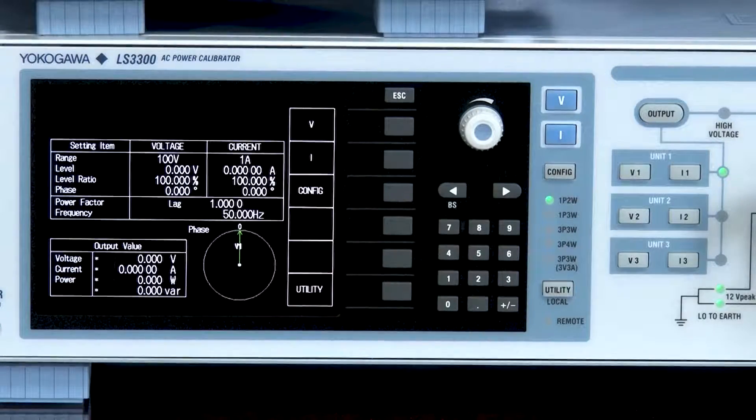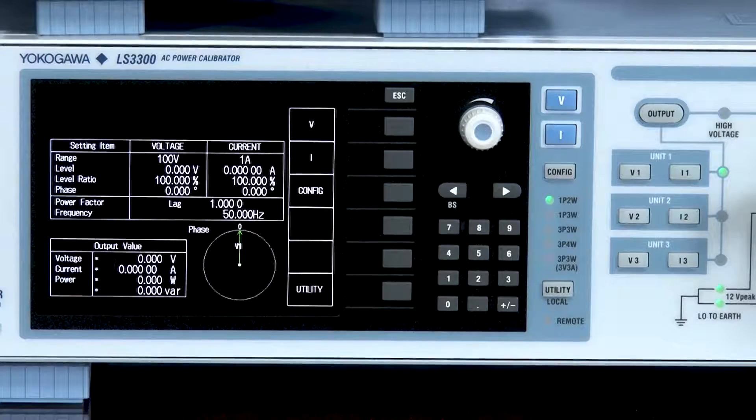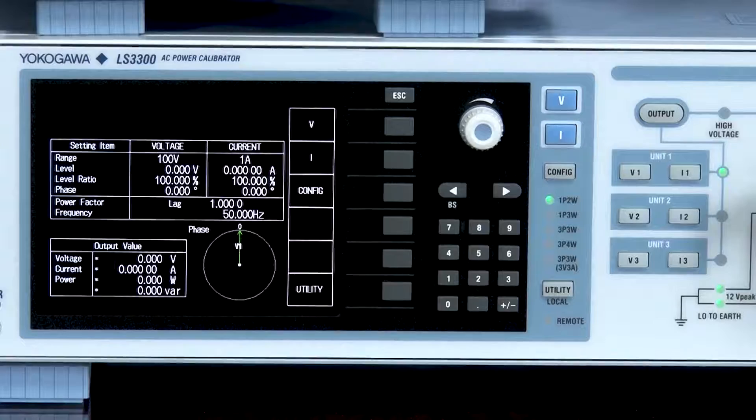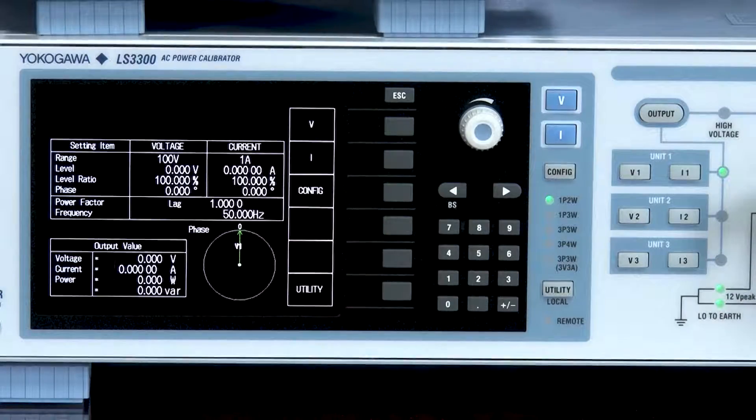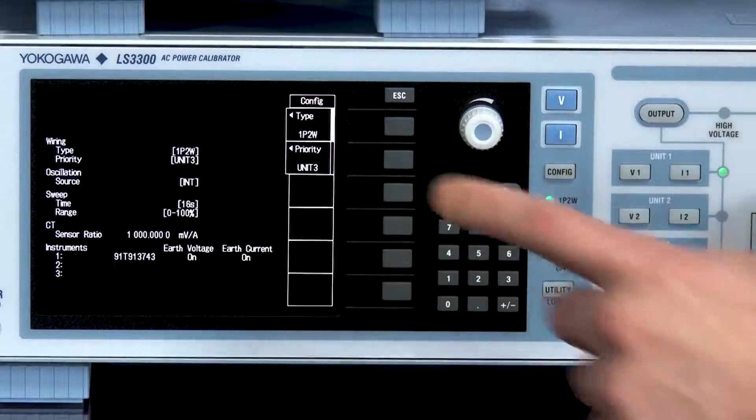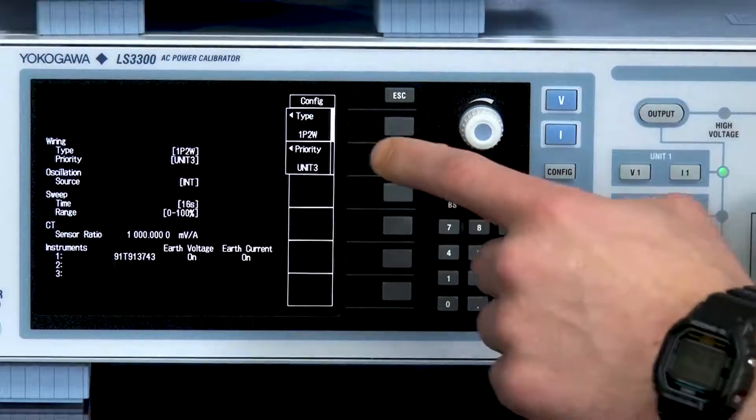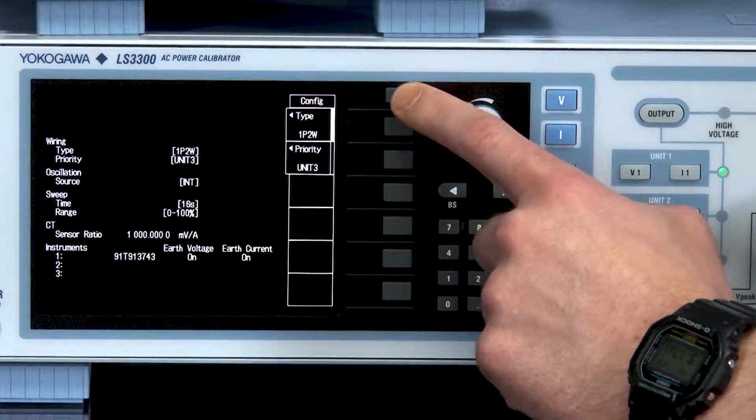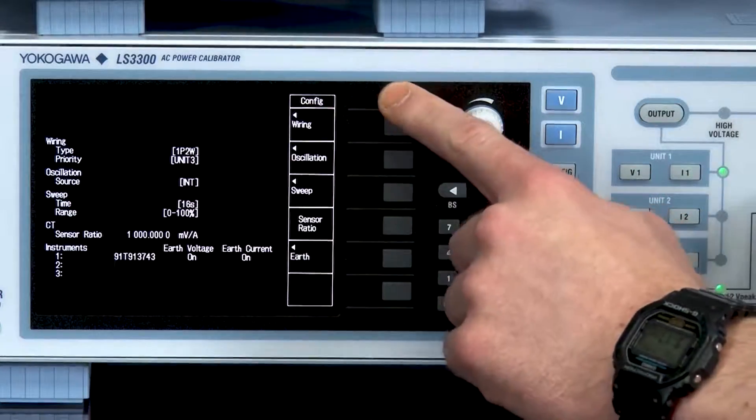The first thing I will show you is how to set up the wiring configuration for one phase two wire in the LS3300 configuration settings. First I will press the configuration key, then I will select wiring next to the type, and finally I'll select one phase two wire. We can exit out of that screen and then exit one more time.